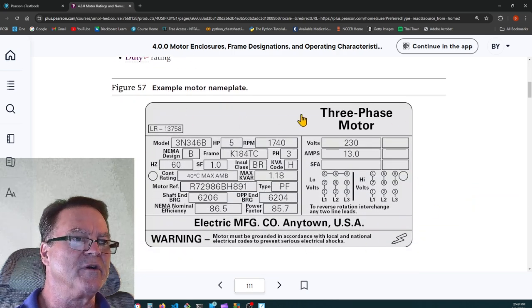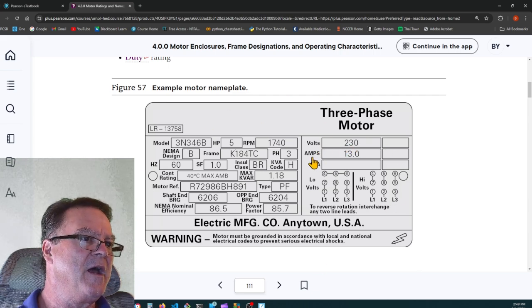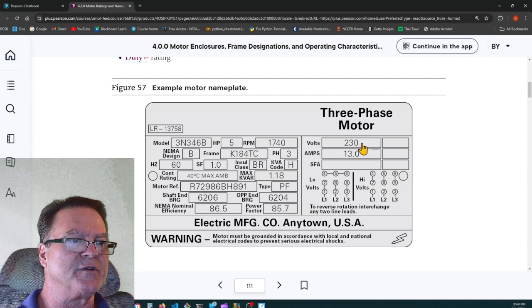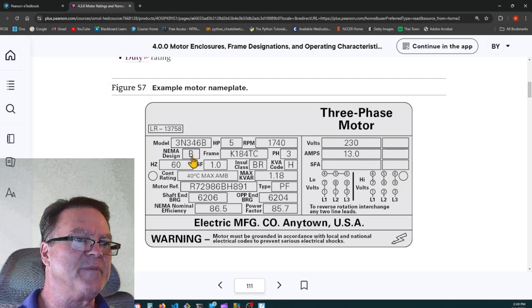So here's a typical motor nameplate. It tells you it's 230 volts. The amps are 13 amps. They're saying it's dual voltage. I don't know why they would show us dual voltage if it only has one voltage of 230 volts. This should either say 230/460 or 120/230, 115/230. NEMA design letter B.